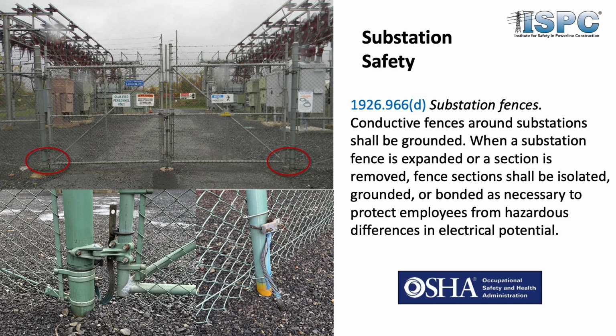Substation safety: OSHA regulation states that substation fences shall be grounded. When we remove a section, expand a fence, or reduce a fence, we need to ground or bond as necessary to keep that protection for our people, to eliminate differences in electrical potential.